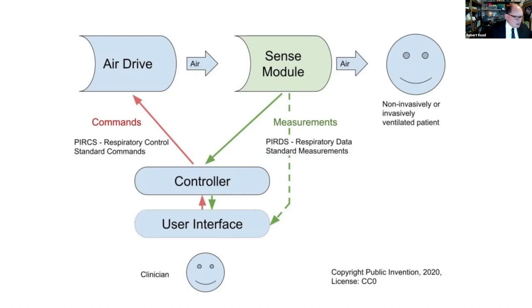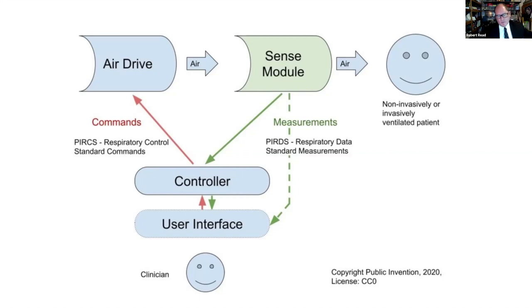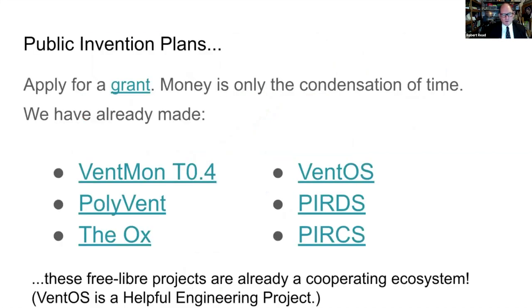You need something like the Ventmon to detect the lowering pressure which is caused when the patient attempts to initiate a breath. But if you have a sense module — as OpenVent Bristol has, for example — then you can support spontaneous breathing, which makes it far easier to deploy, especially in a low and middle income country. The controller is very similar to VentOS. We also have efforts underway to make a user interface.